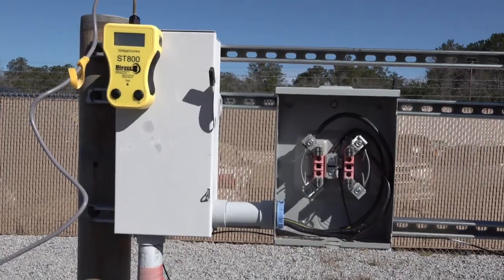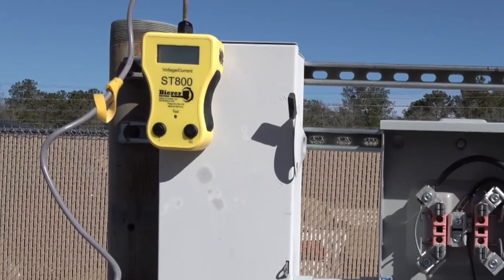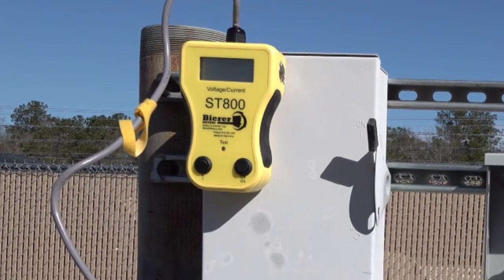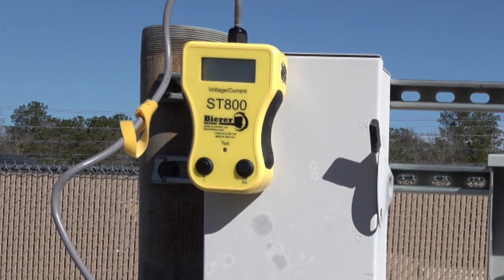The part number ST800 stands for Service Tester 800 amps. This unique tool to the utility industry does two things simultaneously. First, it will test the integrity of secondary conductors, and it will also identify secondary conductors, and there are a couple applications for identifying primary conductors.